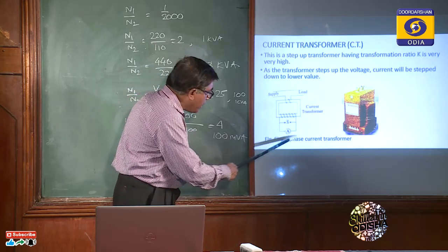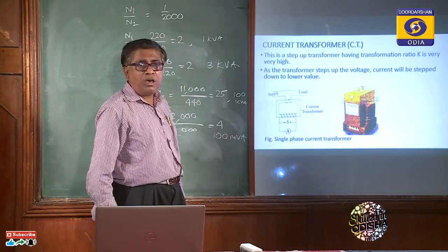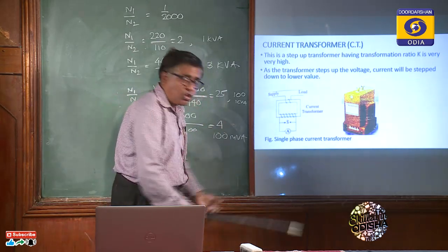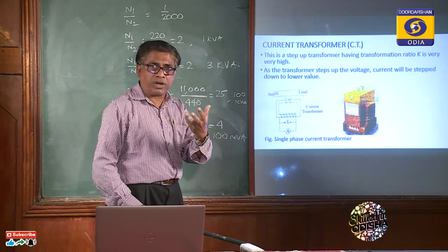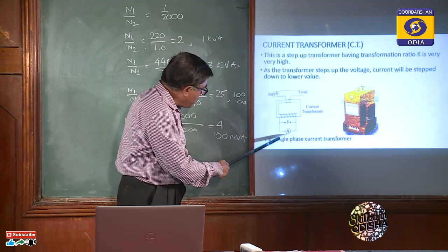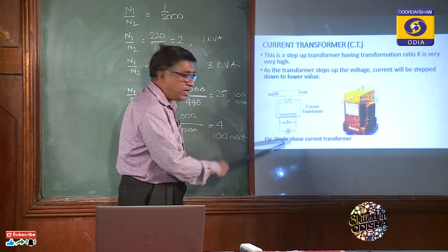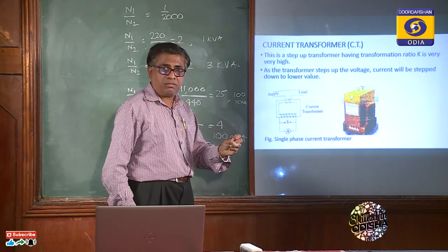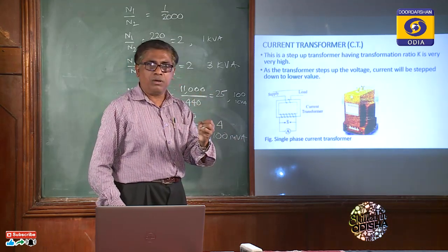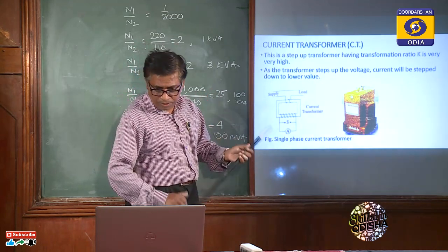Because the range of this ammeter is 0 to 1 ampere. For example, if current coming is 0.1 ampere, the ammeter is showing 0.1 ampere. Actually what is the current? Now 200 ampere. So this CT is helping in measuring the current. Actually current measuring is by the ammeter. CT is helping for measurement of current.